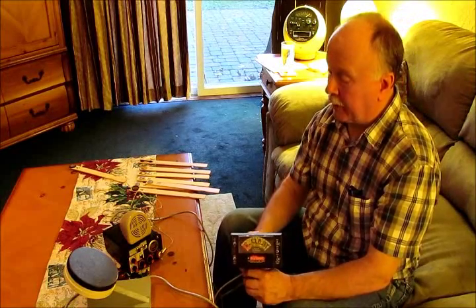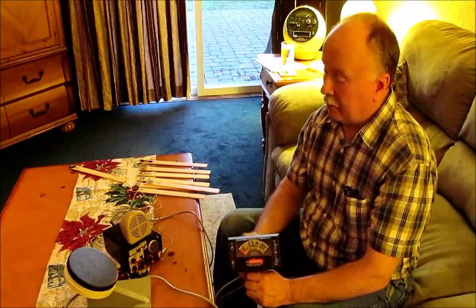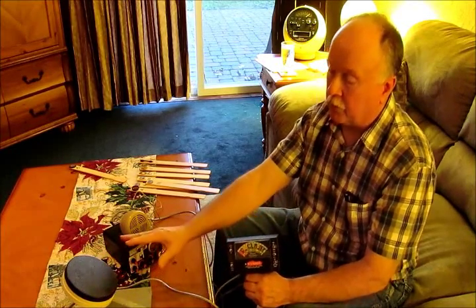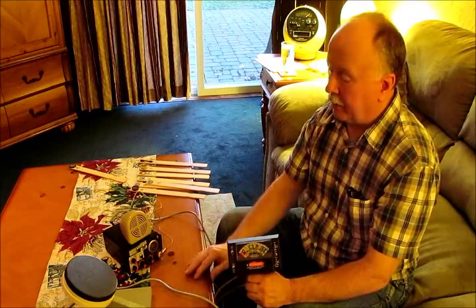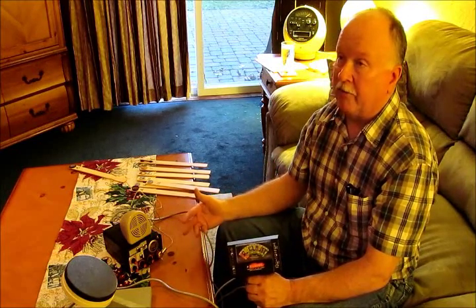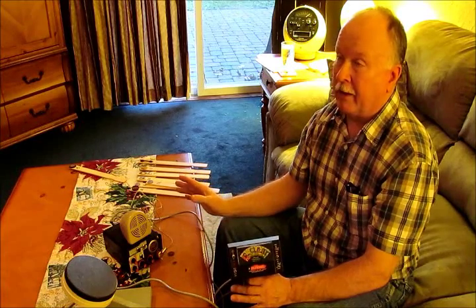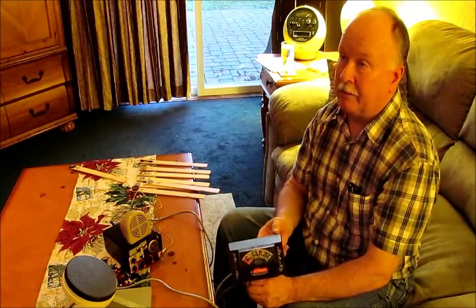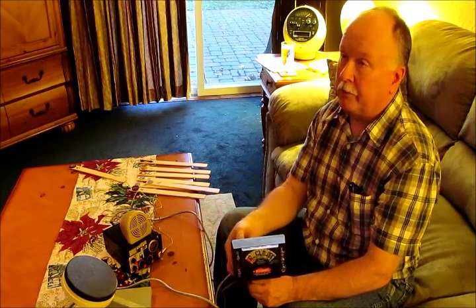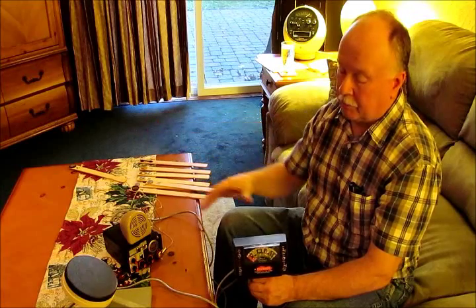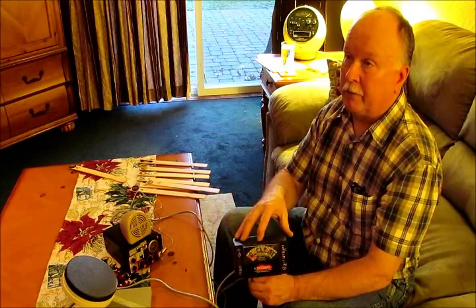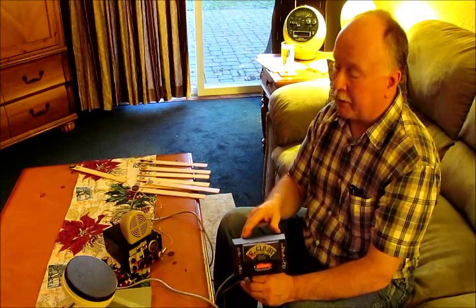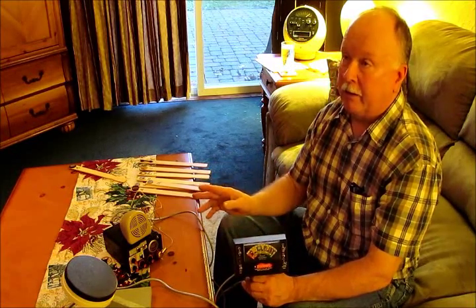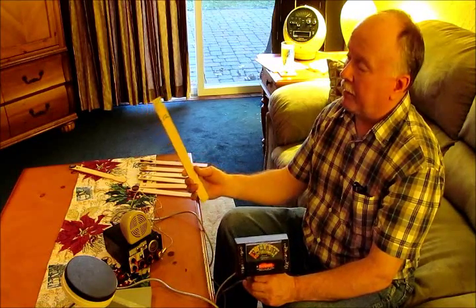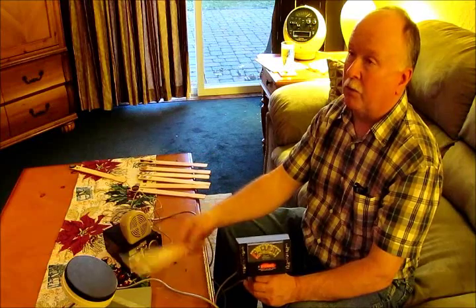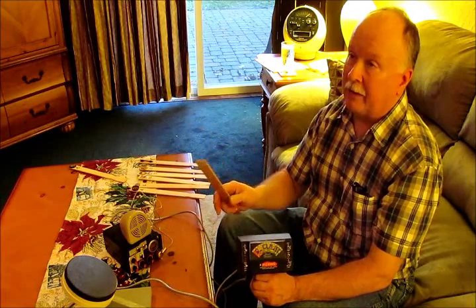Okay, actually what I have here, when I had these in production, this was the actual test fixture that I used for the coil. Just a little stand that I built. And after I would get done going through the calibration procedure with the computer that I had, there's actually a connection inside the meter housing that I connect my computer to, and that goes out to my programming fixture. And it programs all the code or firmware into the meter to tell it what to do and how to interpret readings. And after that's done, I do a double check of every target that I made on little sticks like this that I wave past the coil, just to verify that the meter is in fact calibrated properly.